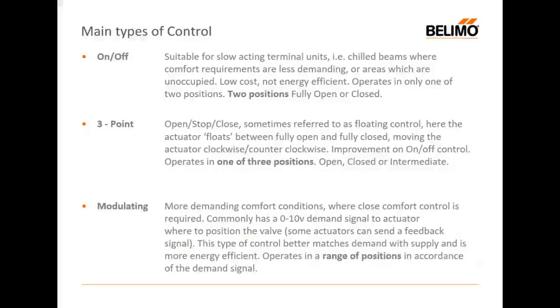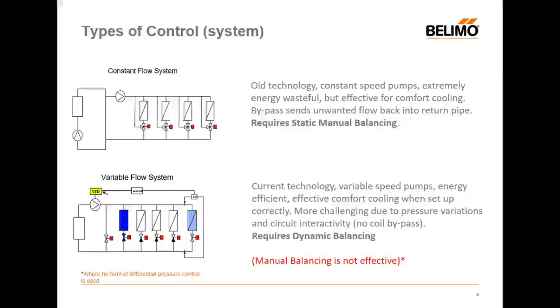And if we want really good control and good comfort conditions, then we should elect to have modulating control. And this is where close comfort is required, commonly arrived at through a 0 to 10 volt demand signal via a DDC controller to an actuator, which is asking the valve to take a position where it can meet the demand of the space we're cooling. And these valves operate within a range of positions according to the demand signal. So we've got very basic on-off, not very efficient. We've got three-point control, a little bit better than on-off, but not as good as fully modulating, and then fully modulating. And so we should look at the systems we're employing.